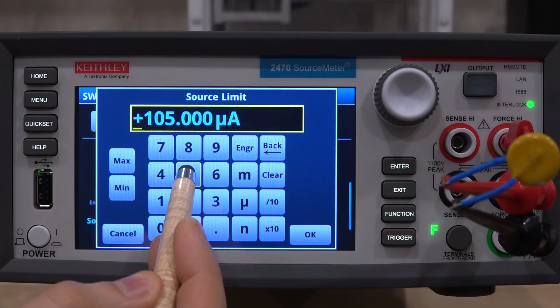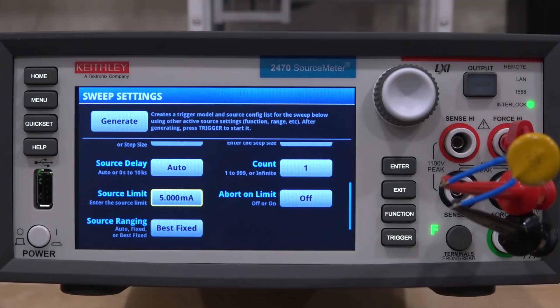I'm going to turn this off so it doesn't stop on a limit. I'm going to change the source limit here to 5 milliamp, so it puts as much as 5 milliamp into the device. Now remember, 5 milliamp, when there are hundreds of volts across this and when it triggers, is actually quite significant.